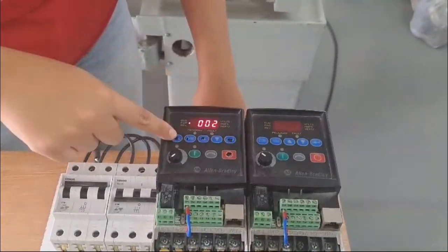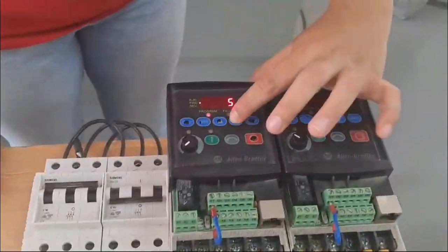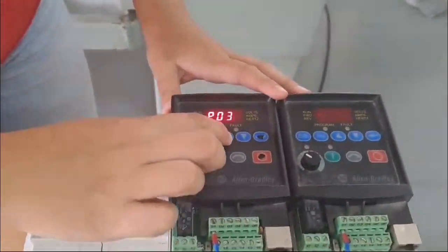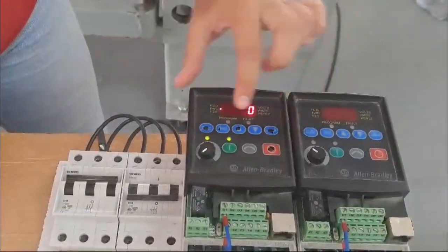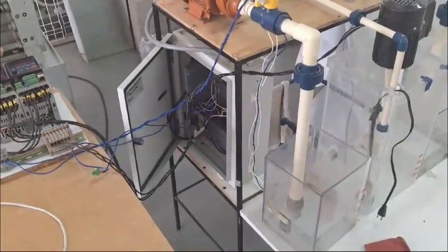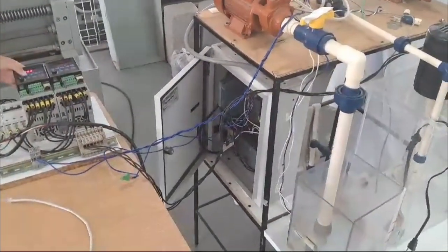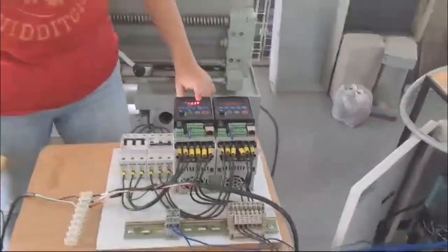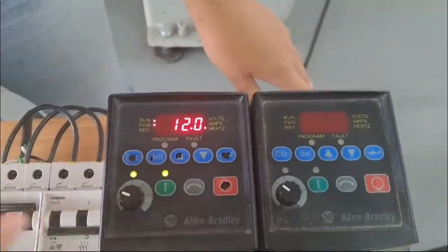As we can see already in the practice, we have the VFD previously connected and all ready to work. Here we make the selection of the corresponding options in the registers mentioned, P038 and P036. Once the keypad and the potentiometer for manual control of the motor frequency are activated, we proceed to vary the frequency from 0 to 15 Hz. We observe that the motor does not go from the state of rest up to the frequency indicated by the potentiometer. The motor takes a response time to reach this frequency. The same happens when you want to slow down or stop the motor, as you can see in the video.